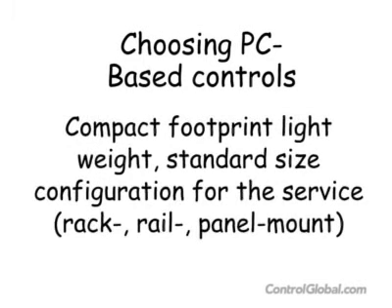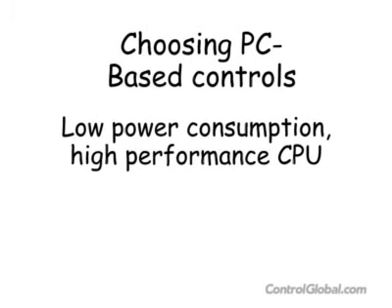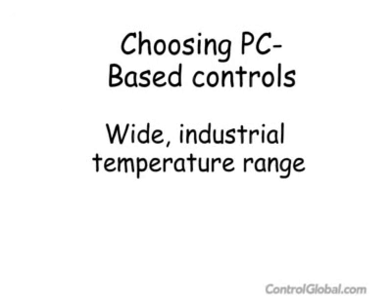PC-based controls should be available in a variety of configurations with the same programming and performance characteristics, whether they're embedded in an HMI or in a panel-mounted device, a rack or DIN rail-mounted device, with as few connecting cables as possible to prevent vibration-based failure modes. The circuit board must be designed for industrial service, not a general-purpose PC motherboard. Components should be soldered wherever possible rather than connectorized, again to prevent failure. And the PC-based controller needs to operate over a wide temperature and humidity range, much wider than commercial products do.